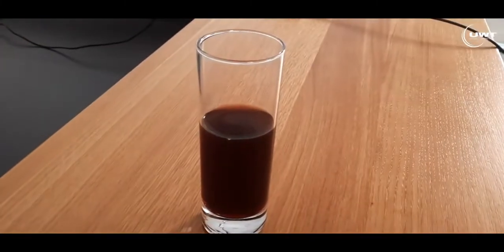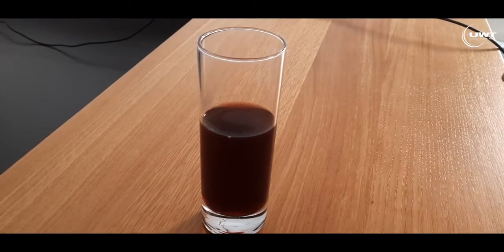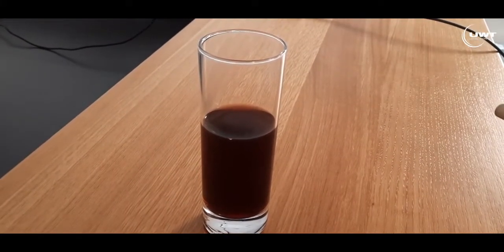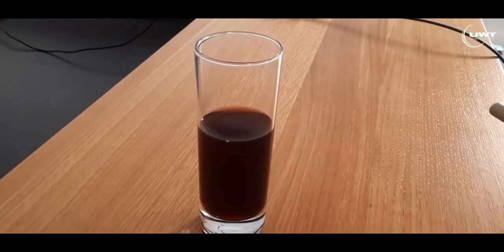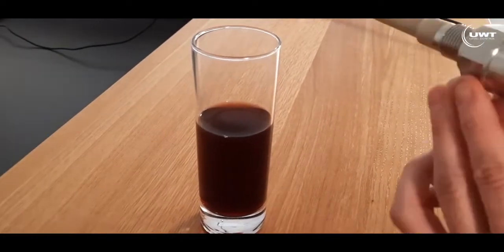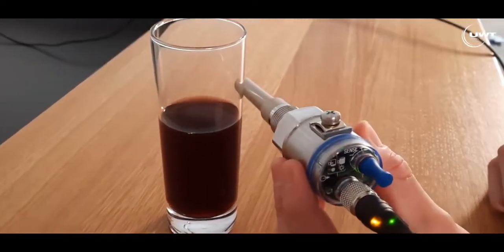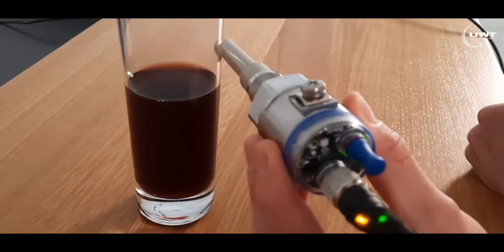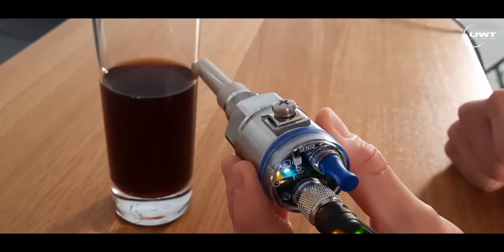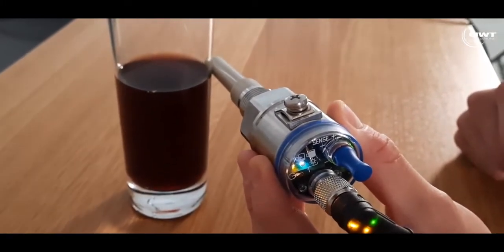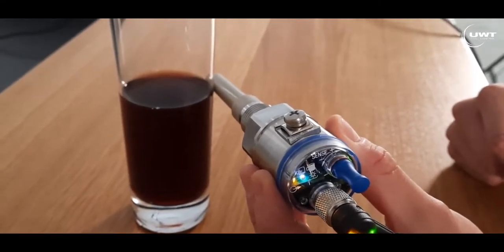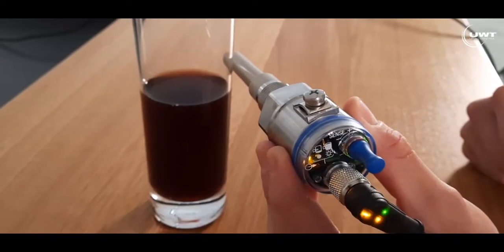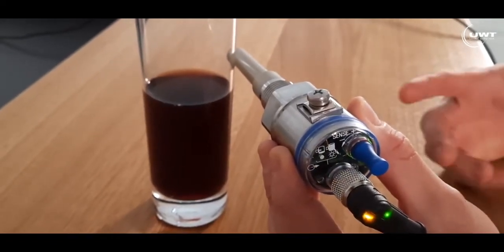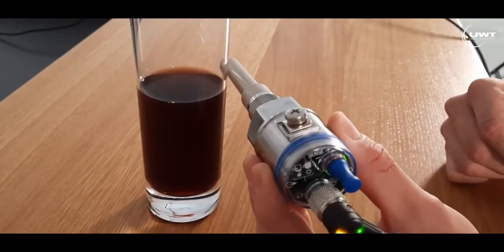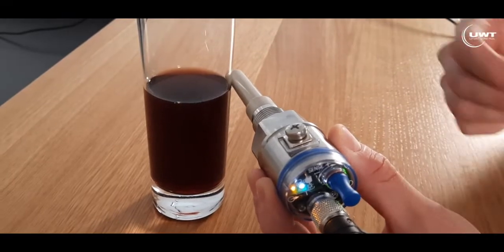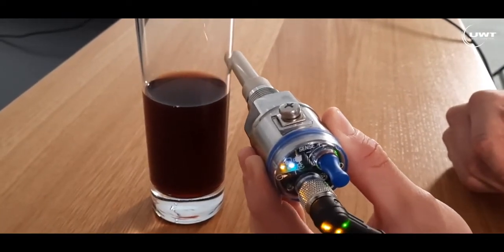The second test I will do is with grape juice. Here I will demonstrate that the sensor does also indicate a material even though it doesn't touch the material, like a measurement from the outside. So here I go near the glass. We do not get a switch signal, and if we're now reaching the material, then the sensor indicates that the probe is covered, that the material is present, and when I move back up, then it switches off again. So this is to demonstrate that the sensor does not have to get into full contact with the material, but a measurement from the outside is also possible.